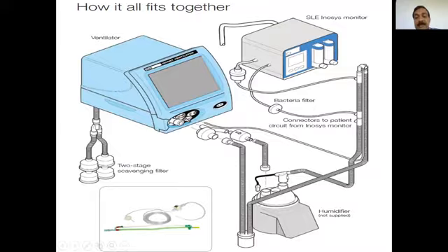And this has to be connected immediately after the humidification chamber. This is where the proximal limb, where the delivery of the oxygen to the baby, the inspiratory limb, is where we connect the nitric oxide delivery. And then this circuit is about 1 foot long, and at the other distal end, the gas that is produced here is monitored through this monitoring system. So it has to be connected to the proximal inspiratory limb after the humidification chamber.